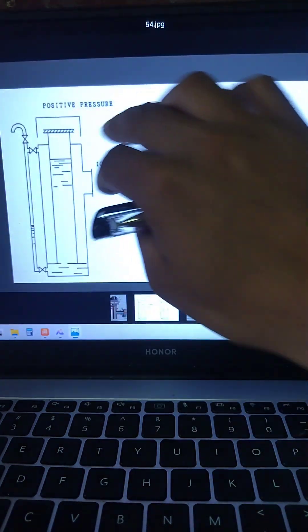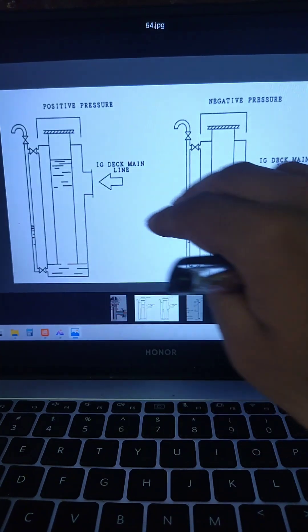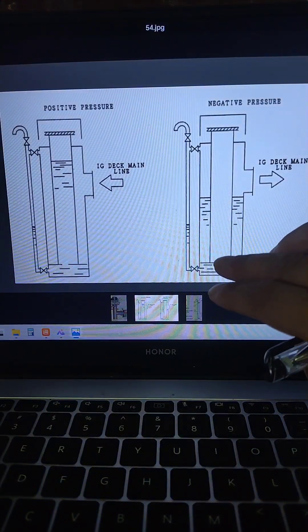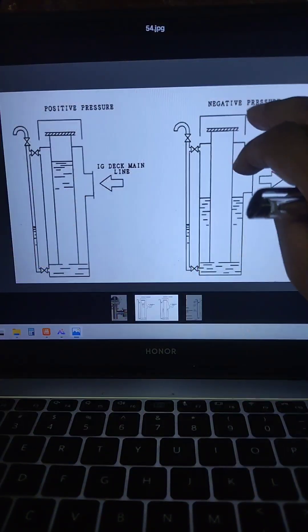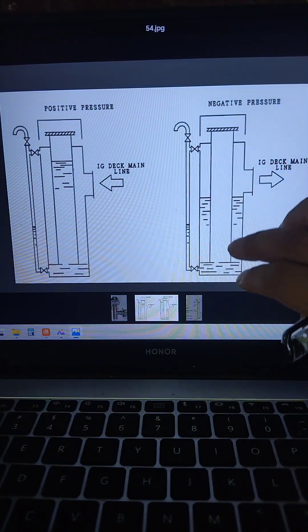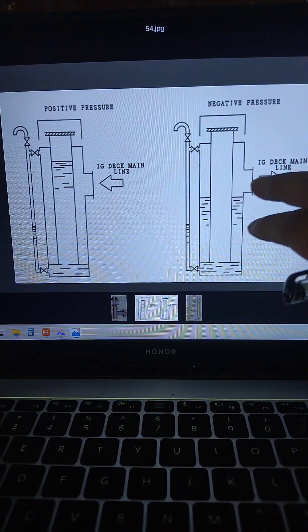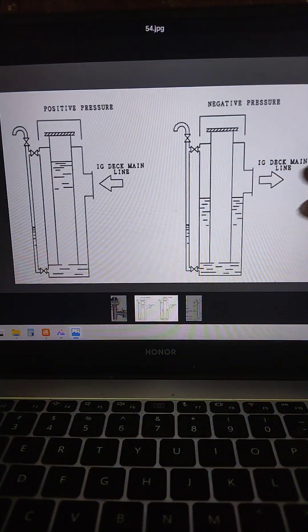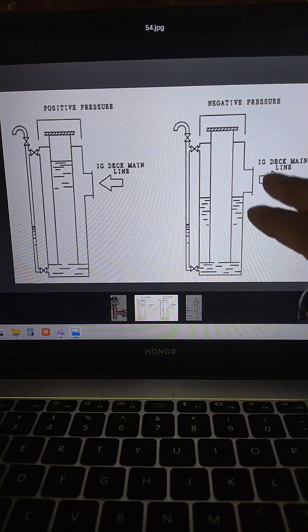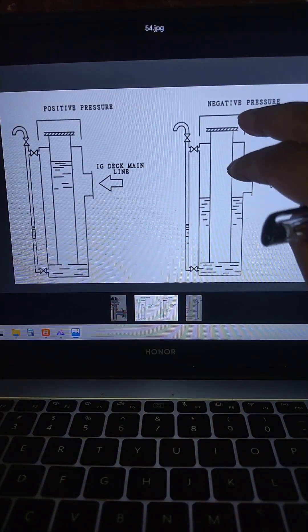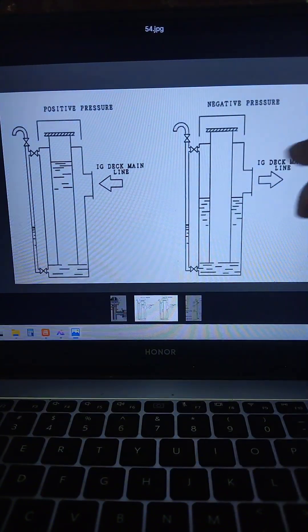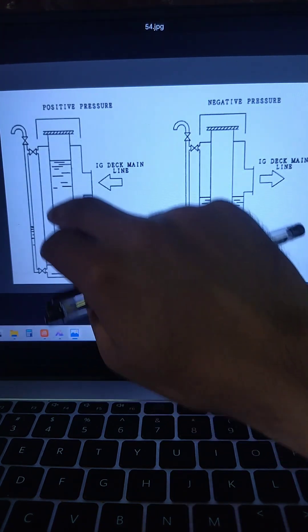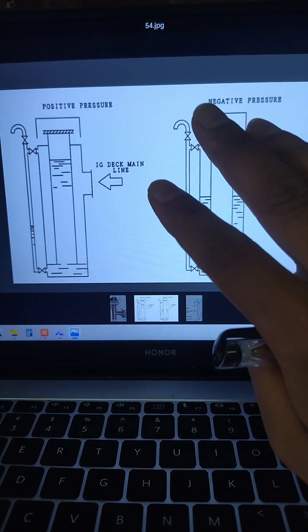Remember: when the set pressure is exceeded, it will activate automatically — that is the vomiting of water. In this diagram, when the IG main line pressure becomes negative beyond the set value, it will suck air from this opening. The water and glycol mixture will go inside the IG line, and after the water goes in, air will also go inside this line to compensate the pressure. In summary: under vacuum conditions it sucks air, and under excess positive pressure it vomits water.